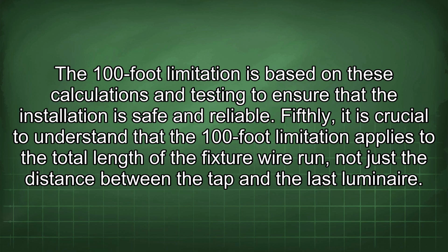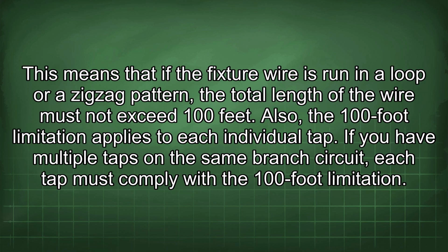Fifthly, it is crucial to understand that the 100-foot limitation applies to the total length of the fixture wire run, not just the distance between the tap and the last luminaire. This means that if the fixture wire is run in a loop or zigzag pattern, the total length of the wire must not exceed 100 feet. Also, the 100-foot limitation applies to each individual tap. If you have multiple taps on the same branch circuit, each tap must comply with the 100-foot limitation.